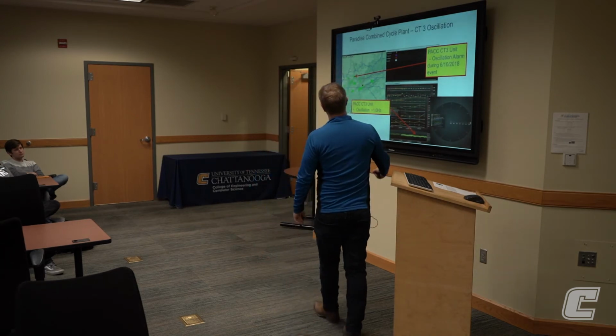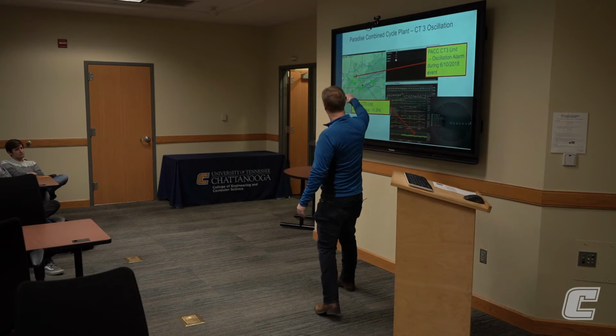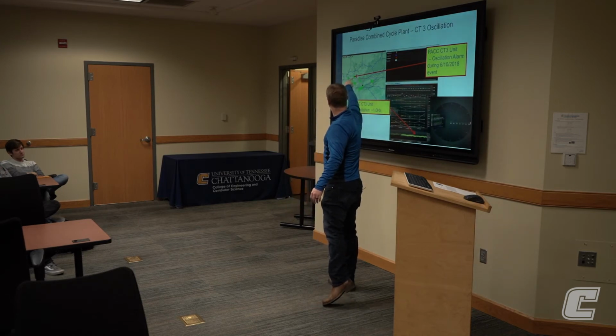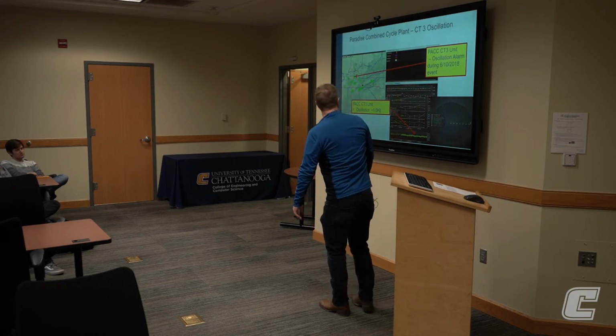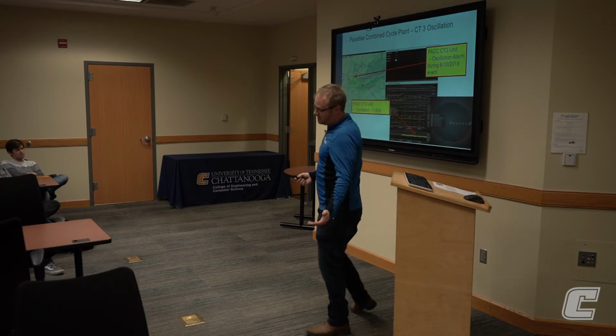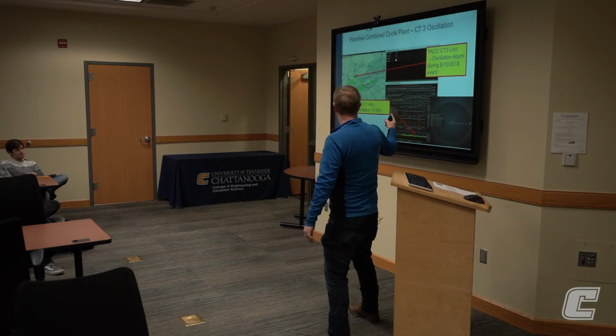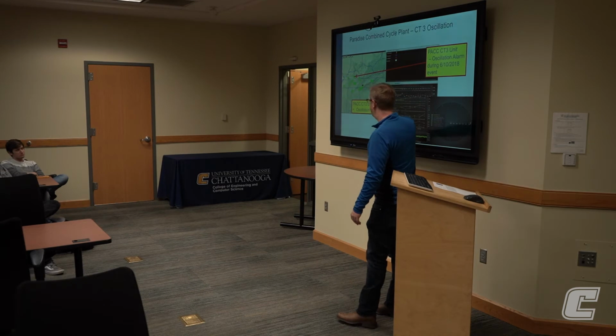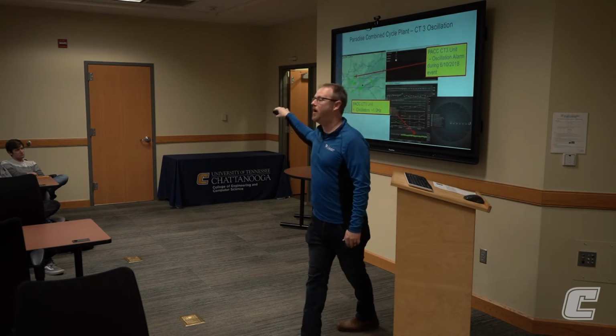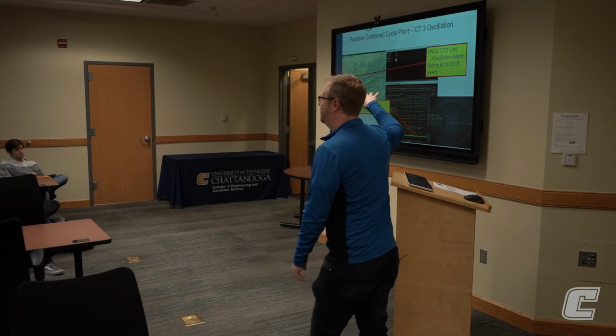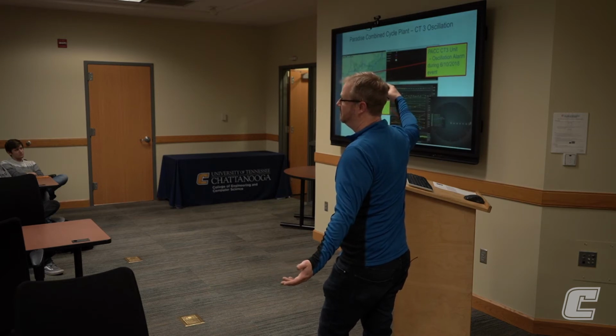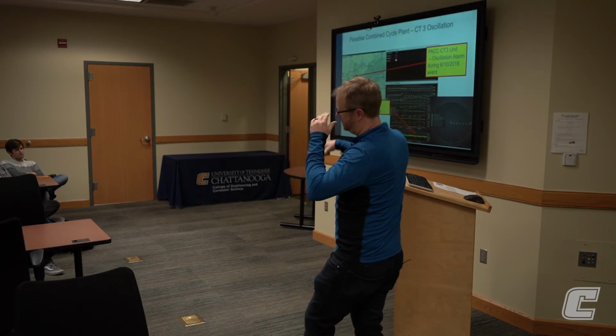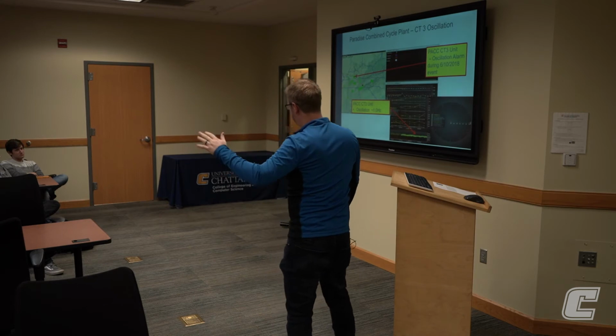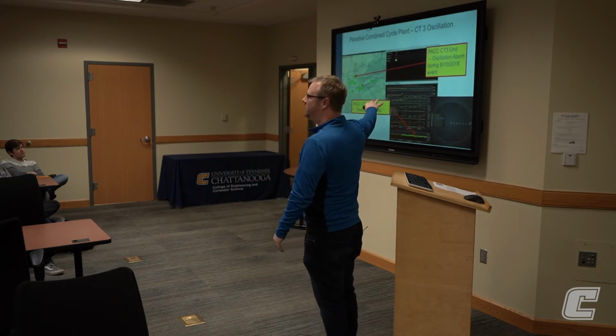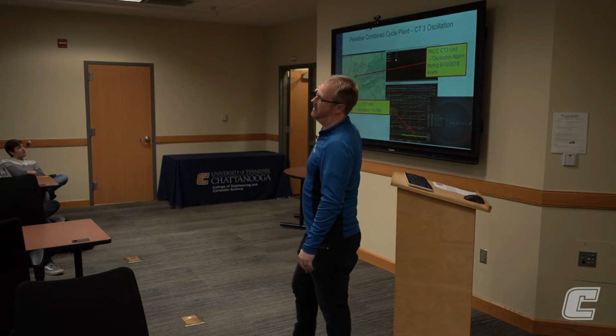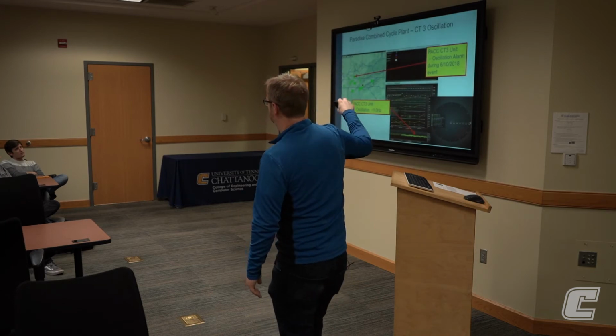So we turn these units up. They're brand new, 3-on-1. That's what the 4 boxes are shown here. And not long after turning it up, commissioning the plant, we got PMU data in. We started getting an alarm in this software, and this is seen by our operators. This is what our transmission operators use to monitor the grid. Okay, one of the pieces of software. Remember SCADA, there's all kinds. But this is what they're looking for. They're looking for these oscillations that could impact reliability or damage equipment.